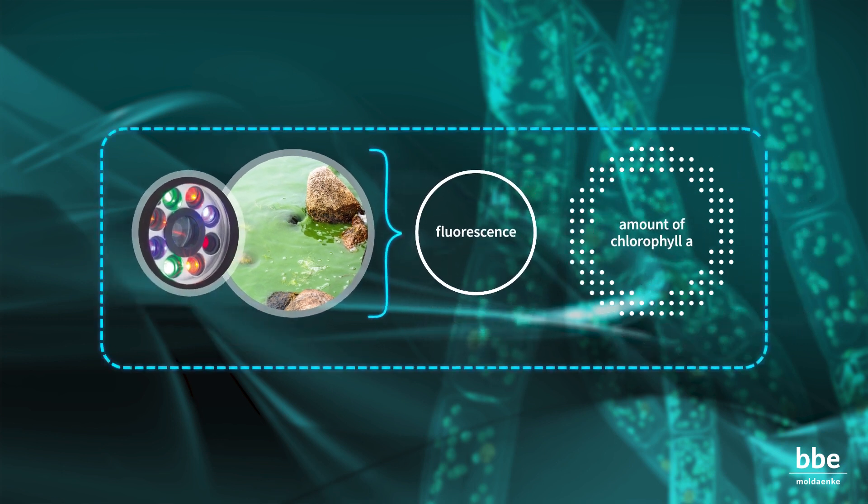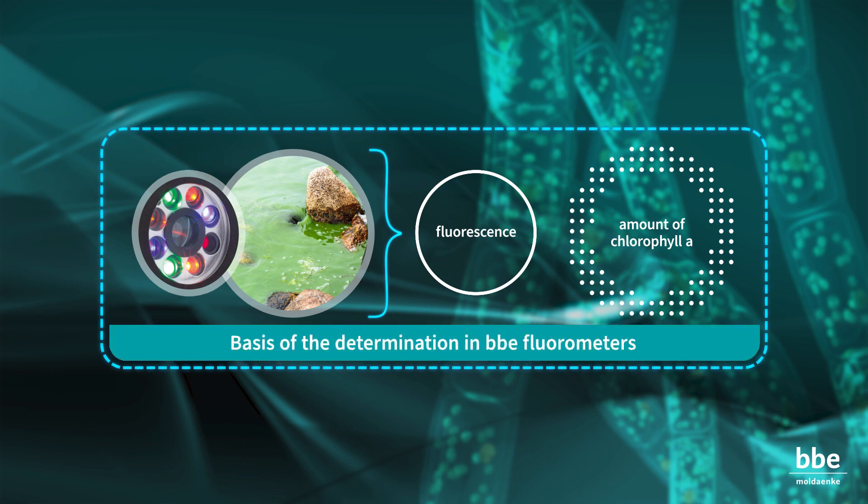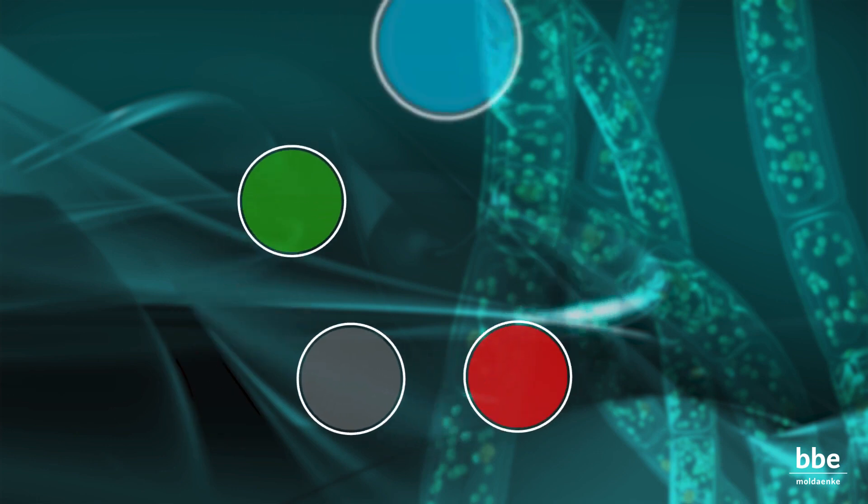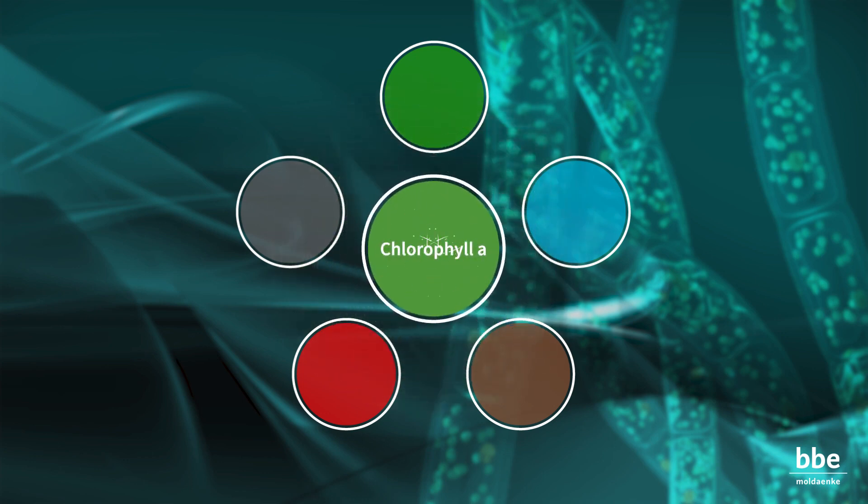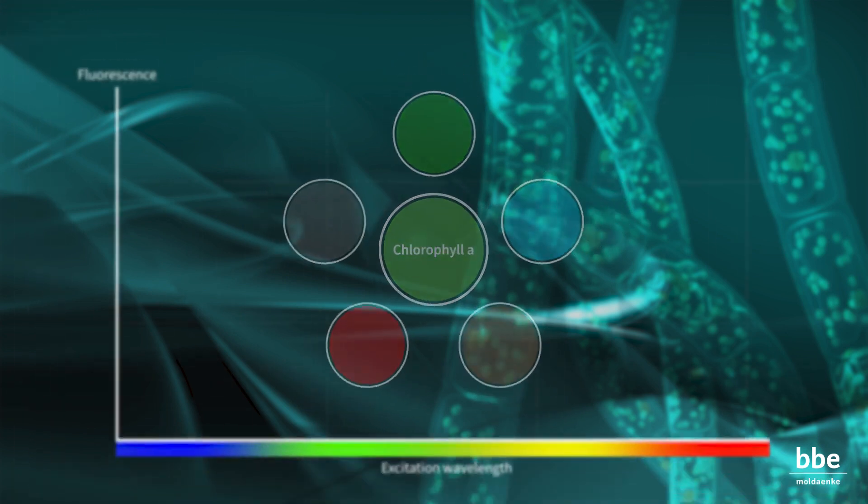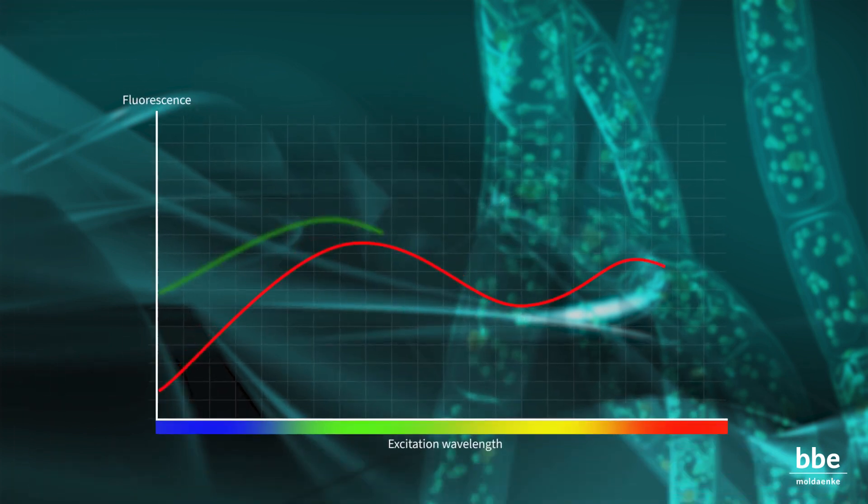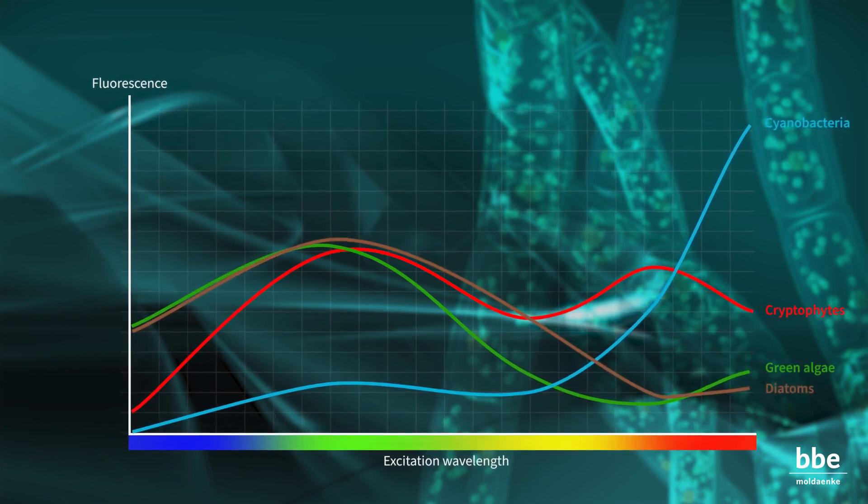This method is the basis of the determination in the BBE fluorometers. Five main spectral classes can be identified, which are related to the different algae pigments. These pigments cooperate with chlorophyll A to transfer the energy of the trapped light. Each class has a characteristic pattern of fluorescence at defined excitation wavelengths.